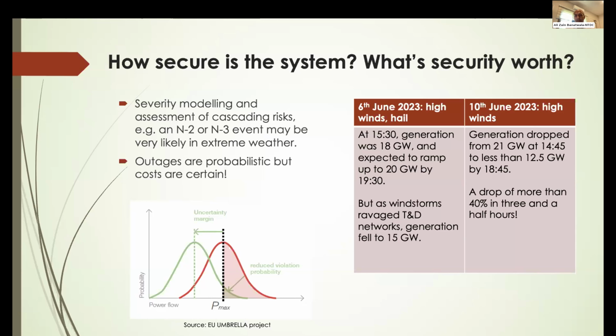This is almost impossible for a system operator to plan for in operational planning, which is usually up to 24 hours ahead using security constrained economic dispatch, typically accounting for N-1 contingency compliance. You might have 10, 12, or 15 critical branches and want your dispatch to ride through disruption of any one of them. But when 5, 6, 8, or 10 branches are affected at once, you simply can't plan for that.